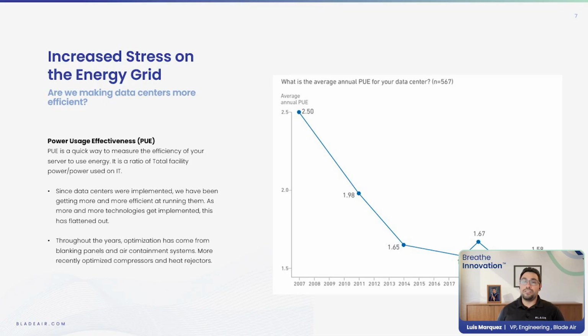Since data centers were created, we've been getting more and more efficient at using energy. At first, PUEs of 2.5 had steadily gone down until that increased usage I mentioned earlier, around 2018. Since then, the average PUE has hovered around 1.5 to 1.6. Throughout those years, there were improvements like blanking panels to block unused aisles, air containment systems, and optimization of layouts and configurations, which led to large initial gains. More recently, technology improvements in compressors, heat rejectors, and fans have led to further gains. However, clearly we're starting to reach the limits of current technology.